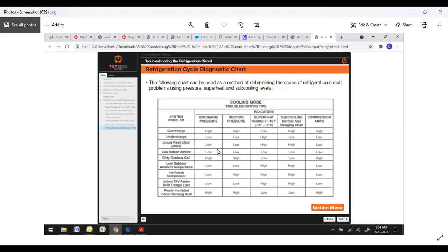So if you have low airflow, obviously your discharge pressure is going to be low. Your suction pressure is going to be low. Superheat is going to be super low. Subcooling is low, and compressor amperage is going to be low. Now, my favorite ones are the dirty outdoor coils. On a real hot day, if you have a dirty coil, if you put your hands on the unit, it's going to be hot because that coil is cooking. If you touch that coil, it's going to be hot.